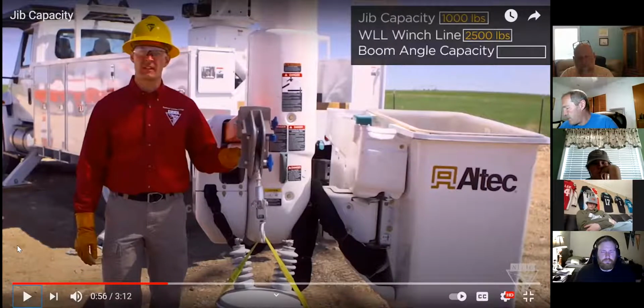Pretty much, guys, that's where it's going to stay all the time, right, Professor V? That's right. Because you're going to be in the bucket, you're going to have to do the work as far as maneuvering the transformer onto the bolts. You put that thing 5 feet away off the jib, you'll never be able to reach it. That's right. You're going to have somebody else climb the pole to be able to reach the end of the jib where you need to stick it out to. So we normally took it no more than 3 feet out as far as the jib was concerned. Go ahead and carry on.